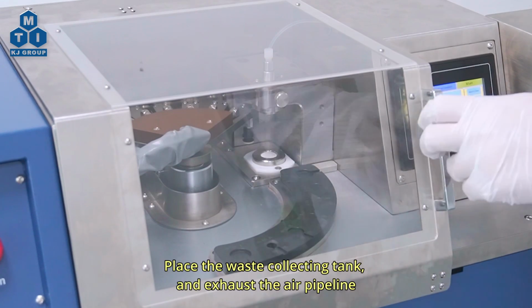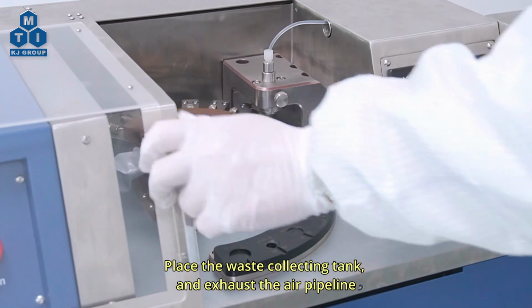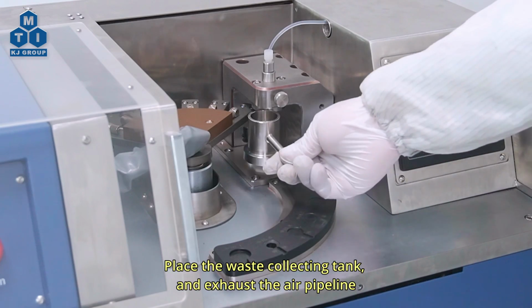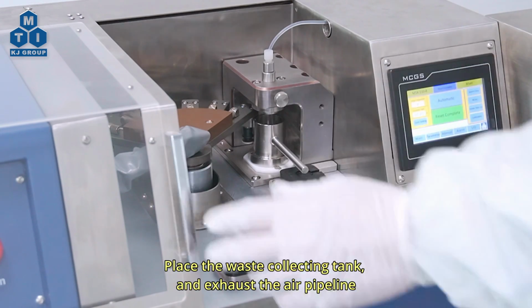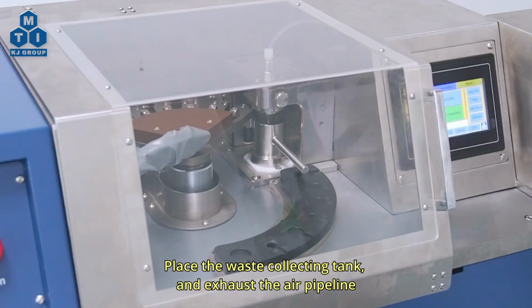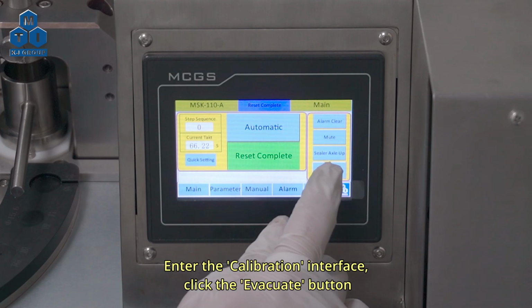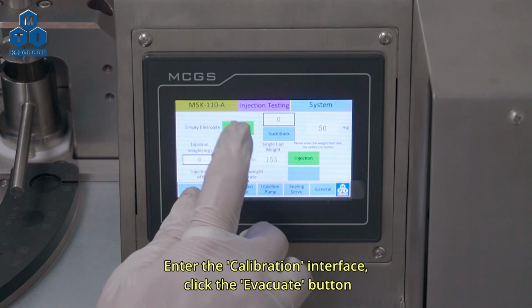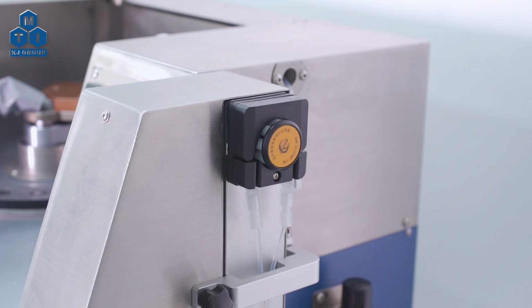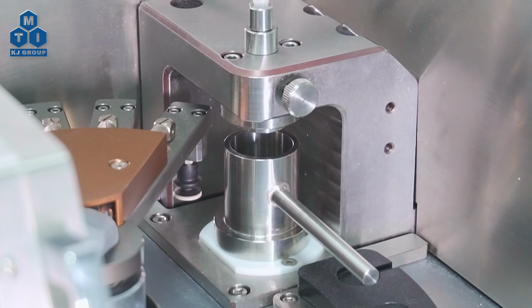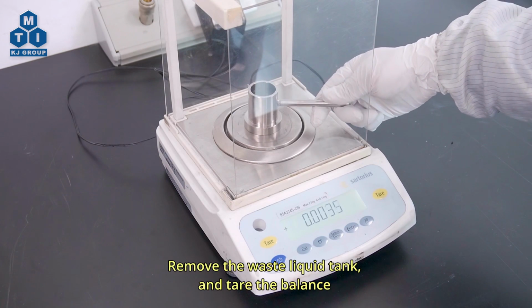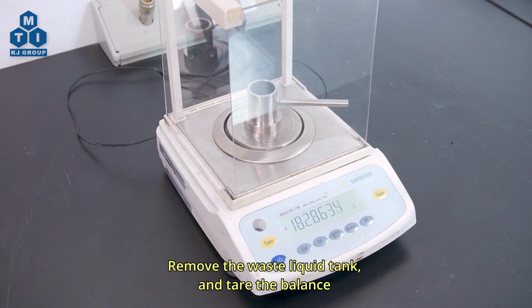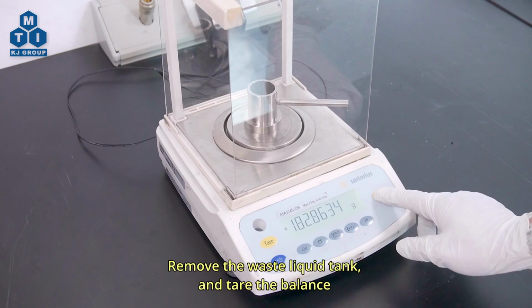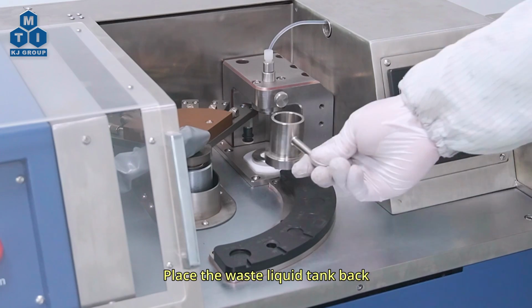Place the waste collecting tank and exhaust the air pipeline. Enter the calibration interface. Click the Evacuate button. Remove the waste liquid tank and tare the balance. Place the waste liquid tank back.